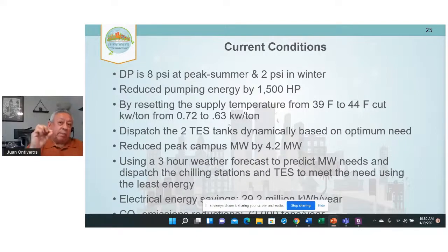When is the exact best time to discharge the tank? We have one tank that's primary, and when we run out of it, we run the secondary tank. That's the way our system is designed now. By doing that strategy, we reduced our peak campus load by 4.2 megawatts.